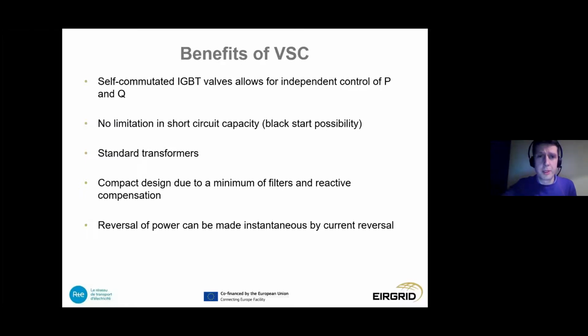The transformers used in VSC schemes are similar to AC standard transformers; they're not exposed to the huge DC stresses that LCC transformers would need to be. We have compact design in VSC, minimization of filters and reactive compensation, and the reversal of power is far more efficient, done instantaneously in a VSC scheme as opposed to LCC.